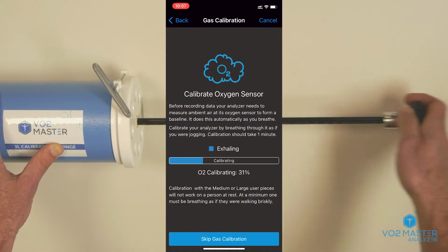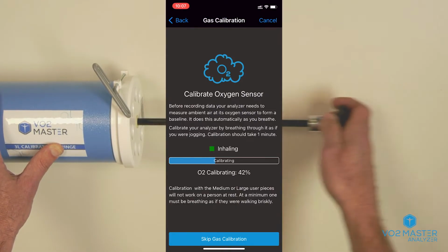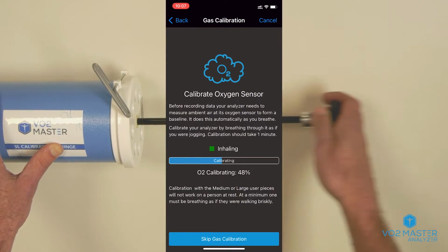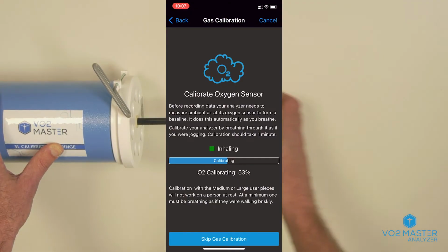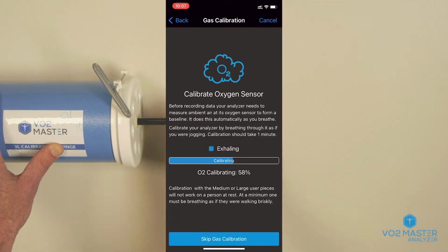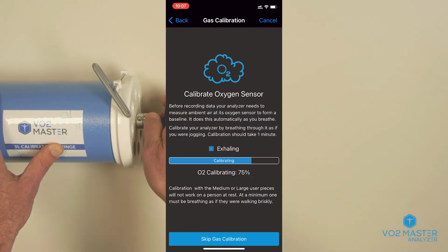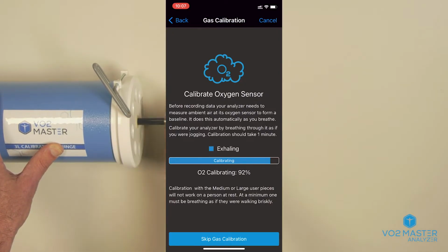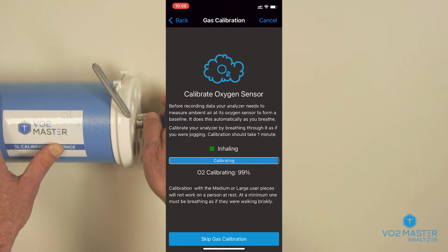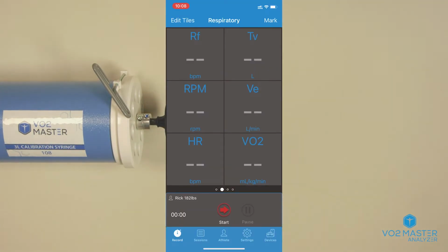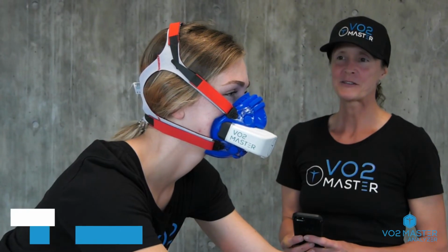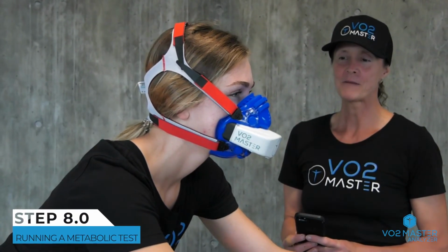However, if you wish to have your athlete calibrate the analyzer, then put it on your athlete and calibration will start when ventilation levels exceed the minimum for the user piece. As we're using the sized medium user piece, we have a minimum ventilation of 30 liters per minute during calibration. Again, keep a good breath rate of approximately 20 breaths per minute and you can calibrate your O2 sensor. Once calibrated, hit next, then hit start and begin your test. Once you have the device calibrated, you're now ready to run your test.